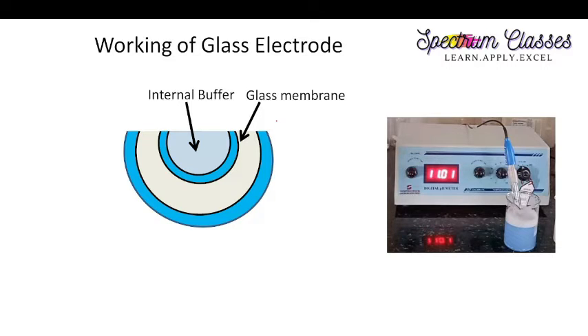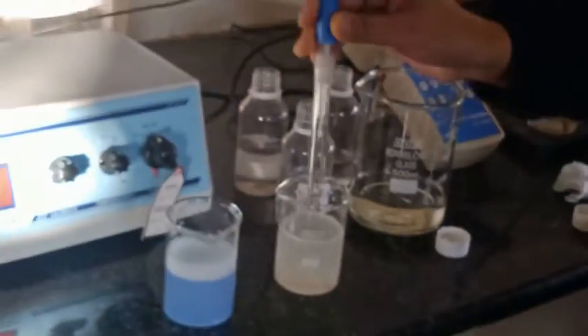When this glass electrode is dipped in the solution, a gel layer is formed both outside and inside the glass membrane. This blue part shows the gel layers; the gray part is the glass membrane. The internal buffer is filled inside the glass electrode. The glass membrane is approximately 0.2 to 0.5 millimeters thick, and the gel layer is 1000 angstroms, or 10 to the power of minus 4 millimeters. These are the approximate dimensions of the gel layer and the glass membrane.